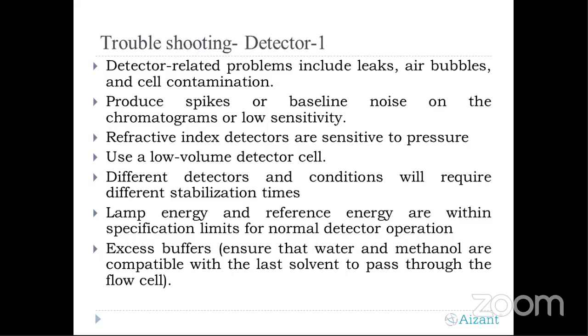And how can you remove air bubbles? Simply disconnect the column, attach a union, and prime the pump first with water. As I told you in the pump section, you prime first with water, then with IPA, then methanol, and vice versa. The same you can connect through a union to the detector. There is a recommendation for the detector on how much flow you can apply. Pressure is limited there and should not exceed a certain value, so please take care of that. If somebody directly starts with a 10 ml flow, it will create a major problem. Your cell can be destroyed. So better to start with 0.5 ml flow, then increase to 1 ml, and the maximum I can recommend is 2.5. Never exceed about 3 ml for any detector. If you have air bubble entrapment, flush the detector for almost 5 to 10 minutes, then reconnect, equilibrate your column and start the analysis.